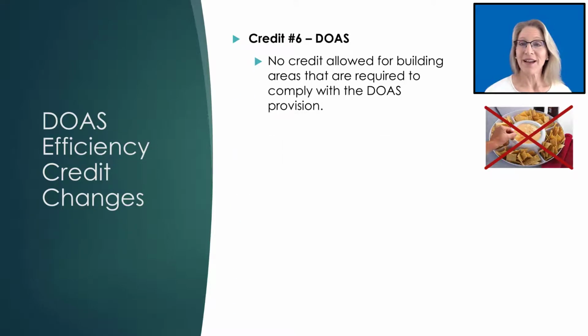First of all, spaces that are required to comply with the DOAS provisions are no longer allowed to take credit for this to meet the required additional efficiency credits. So in other words, no more double dipping.